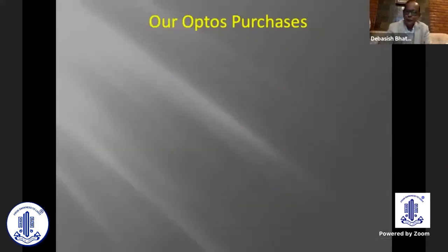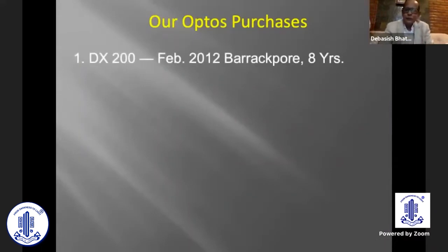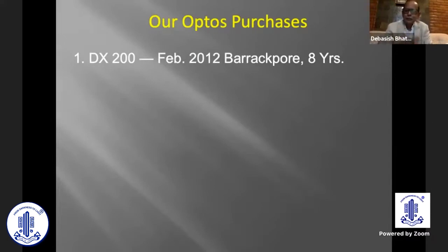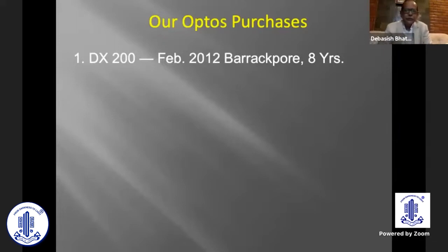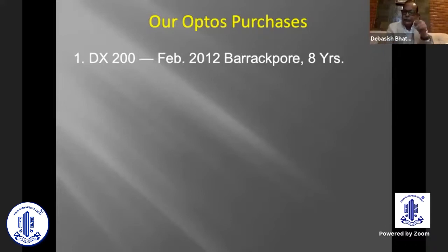How we evolved: in February 2012, after we went to the American Academy, we saw this equipment. I did my own Optos and was fairly convinced, and because retina surgeons are so busy I thought we should buy this as we have so many myopic patients who in a busy comprehensive care setting do not get a full comprehensive retinal evaluation. That was eight years back — telling our experience of the DX200, which can also do angiography. There is something called a polygon which we changed three times; it cost us six thousand dollars each time. That was the entire maintenance on this equipment; it is still functioning and we do our peripheral angiographies with this machine.